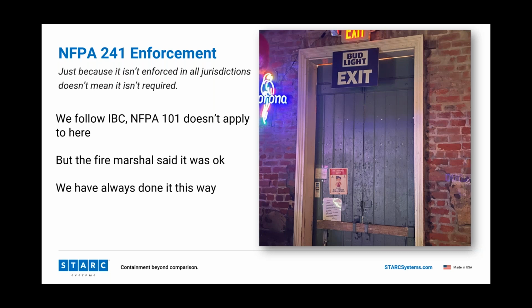Just because the fire marshal says it's okay does not make it the right thing to do. I've got an example. I actually had a smoke evacuation system where, and I still have the letter to this day, the fire marshal signed off that I could remove the beam detectors, and those were the only things that activated that smoke evacuation system in this atrium. Clearly not construction related, but the fire marshal told me it was okay. That doesn't make it okay though.